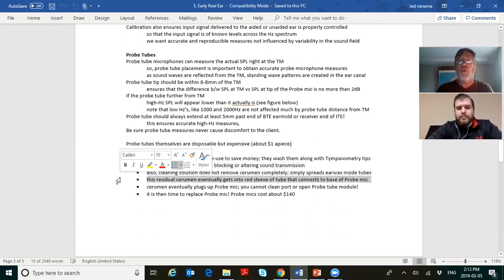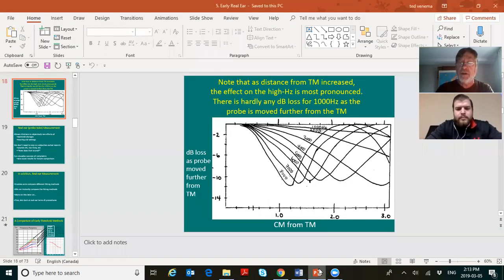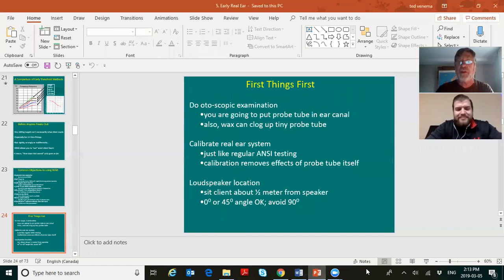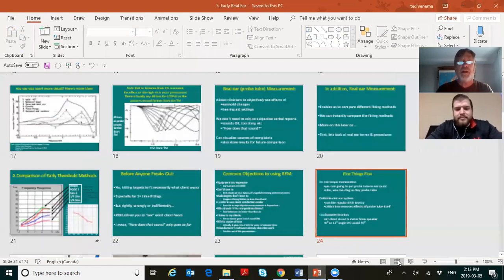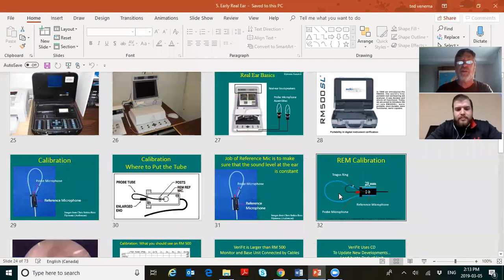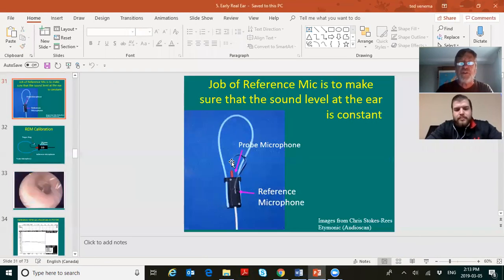This residual wax eventually gets into the red sleeve of the tube that connects to the base of the probe mic. If you're thinking I'm talking in Chinese here, what I am talking about is basically this picture right here, and in different systems, it's in different places. But on the Verifit system, it may look red like this. On other systems, it might be blue. Who cares? But this is where the probe mic is. This is just the tube extending from the probe mic. You'll want to make sure wax does not get inside that probe mic.